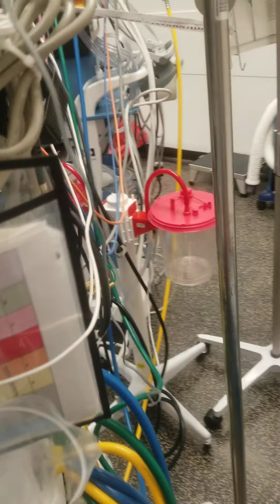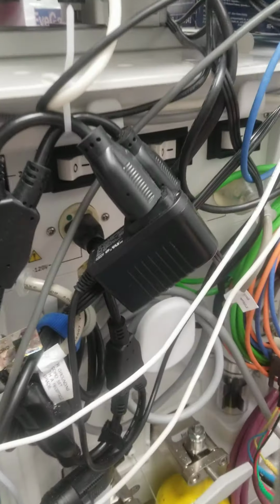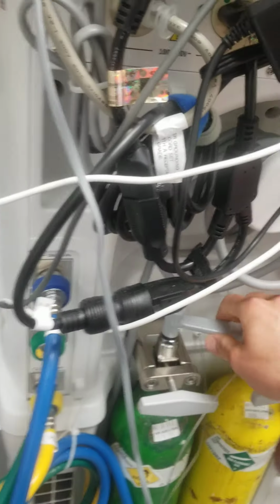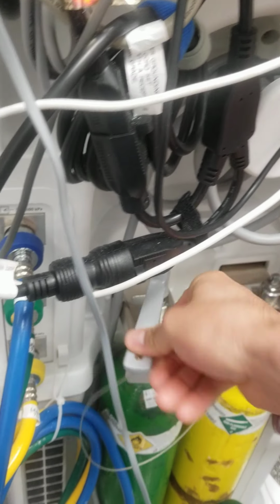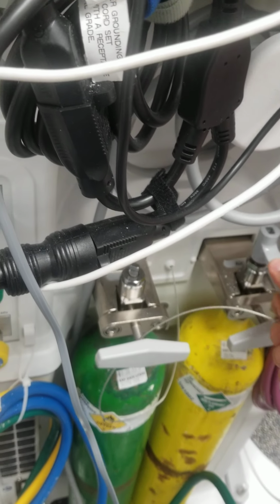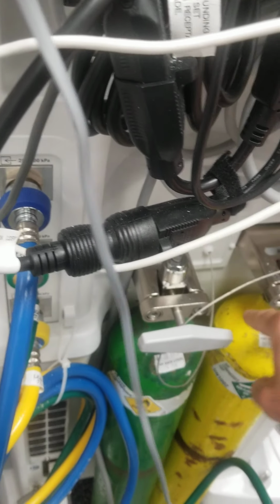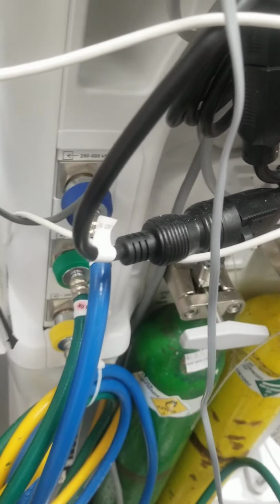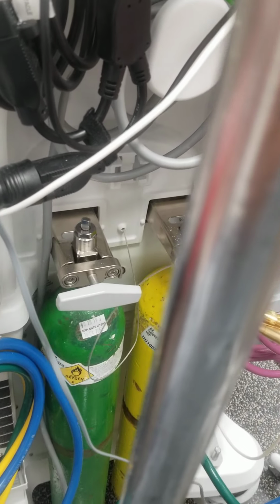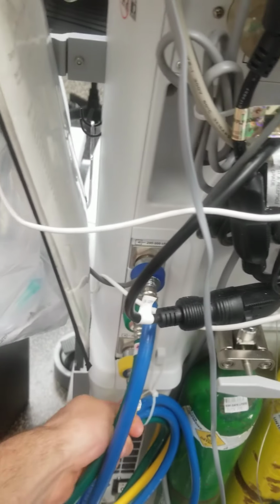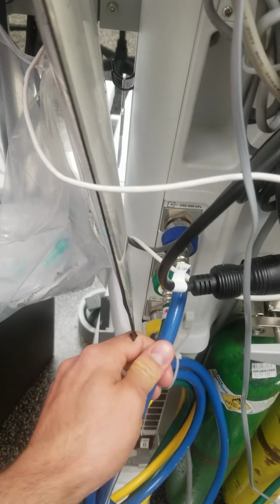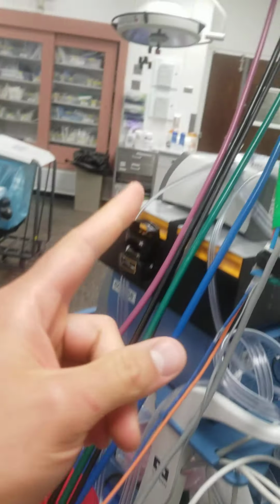I'm going to quickly open up my cylinders for my emergency oxygen, crack it open about a quarter way, close it. That's going to create a pressure between the bottle and the machine to show us what the most recent pressure of these E cylinders is. So open, close. These are my main gas lines. So I have air, oxygen, nitrous. I'll follow those up to the ceiling.